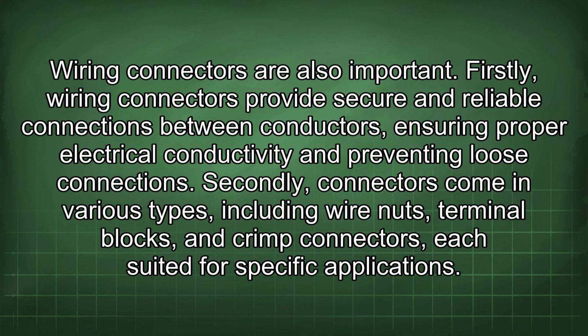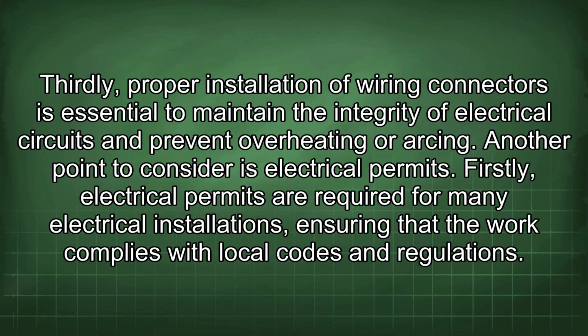Wiring connectors are also important. Firstly, wiring connectors provide secure and reliable connections between conductors, ensuring proper electrical conductivity and preventing loose connections. Secondly, connectors come in various types, including wire nuts, terminal blocks, and crimp connectors, each suited for specific applications. Thirdly, proper installation of wiring connectors is essential to maintain the integrity of electrical circuits and prevent overheating or arcing.